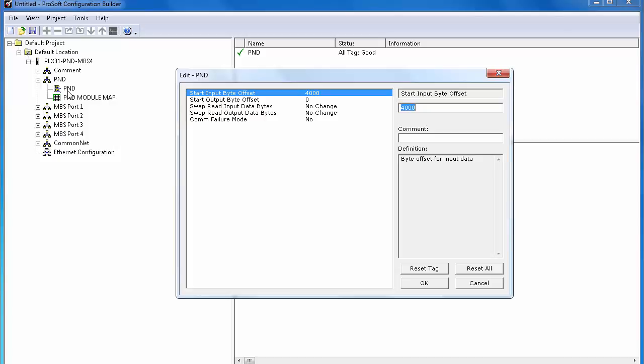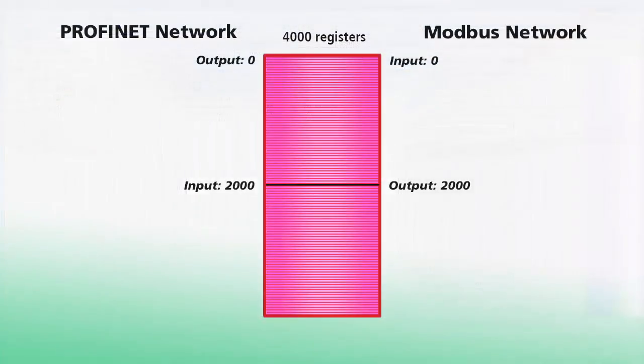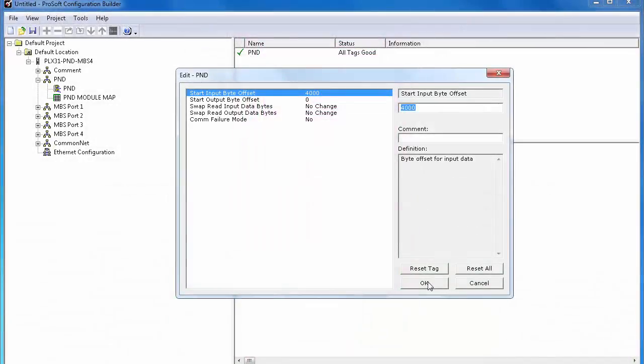Here you can see the input and output for the byte offset inside our database. Essentially, we're selecting the size of the input and output sections for our internal database and where we want them to begin. A byte is half a word, so the input byte offset of 4000 is word 2000. Matching up to our MBS output of 2000 and the output of 0 matches our MBS input of 0.